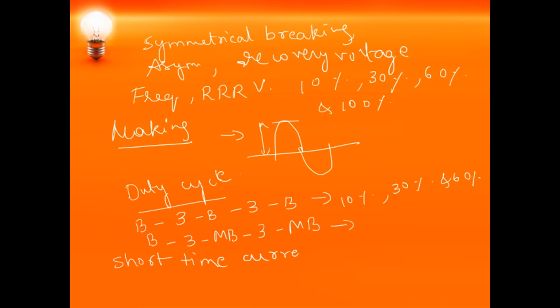Short time current test is nothing but the short circuit current is made to pass through the circuit breaker under test for a specified duration, say 1 second or 3 seconds. The short circuit current which is flowing for that 1 second or 3 seconds is measured by using an oscillograph, and the short circuit current flowing through the circuit breaker should not damage the circuit breaker, because fault current is flowing, is it not?